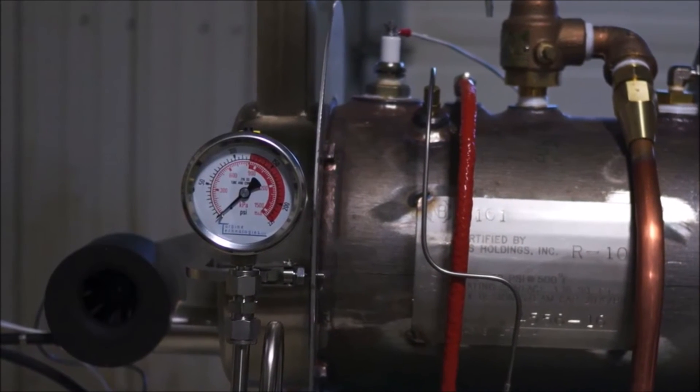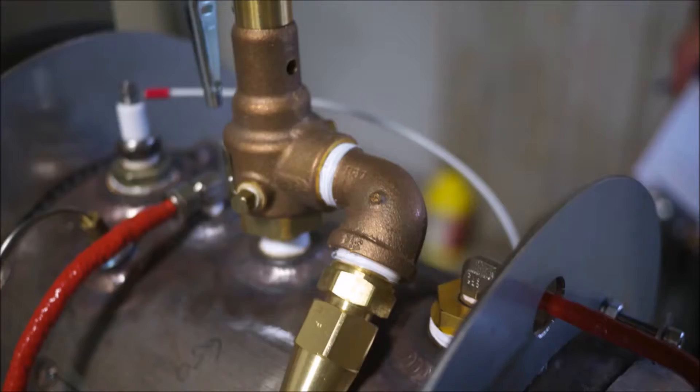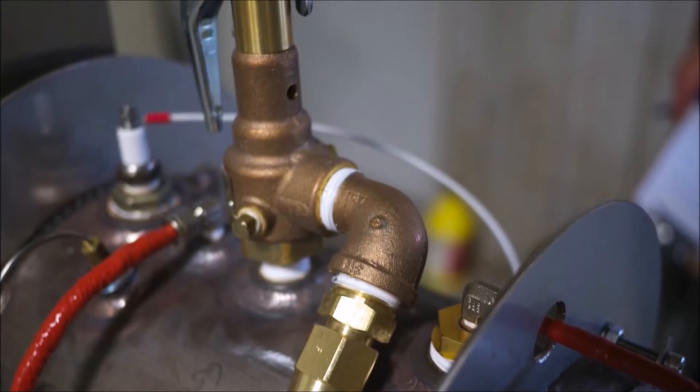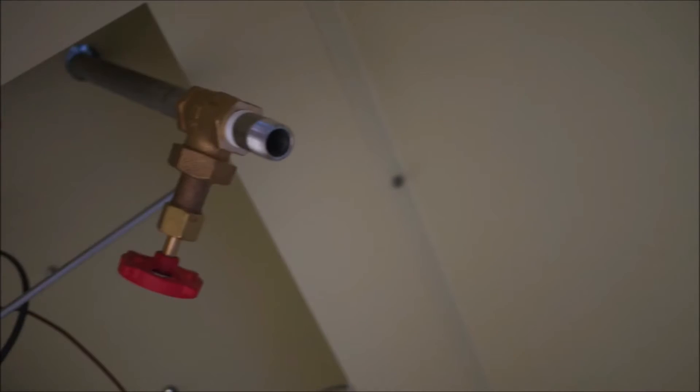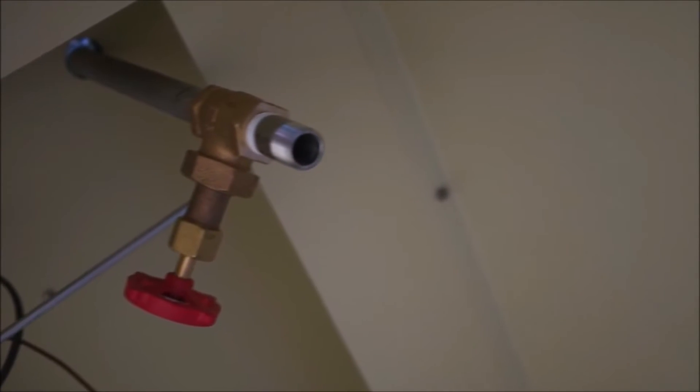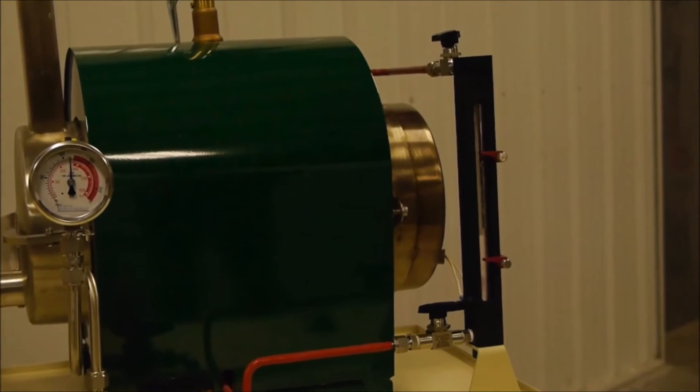It features multiple safety devices for burner operation and system pressure including an automatic overpressure relief valve, an automatic low-water level cut-off sensor, and a manual system blow-down valve. A sealed sight glass indicates boiler water level.